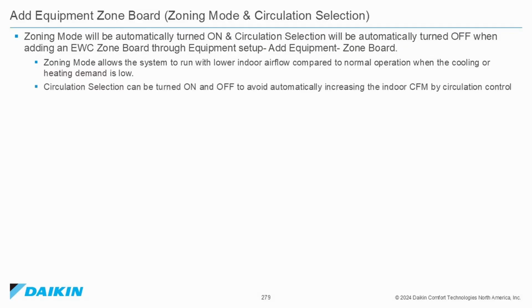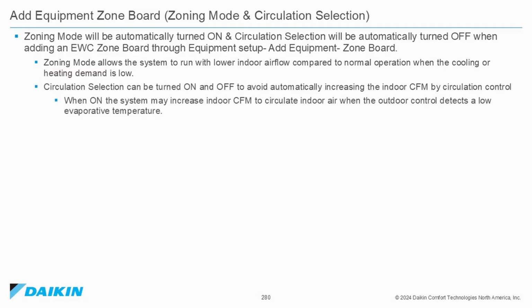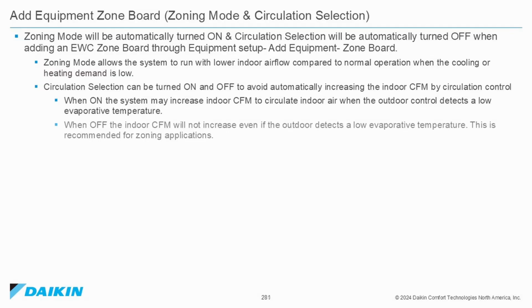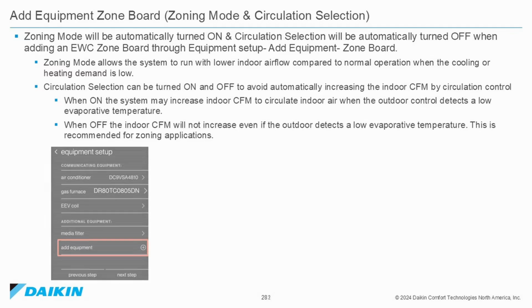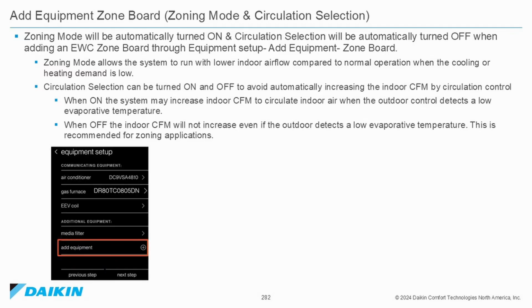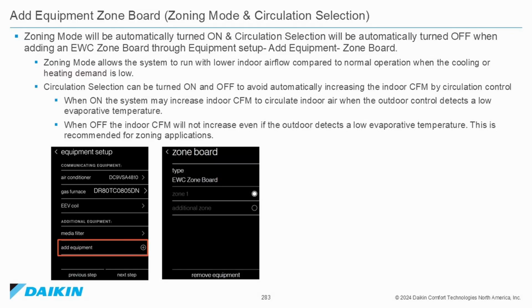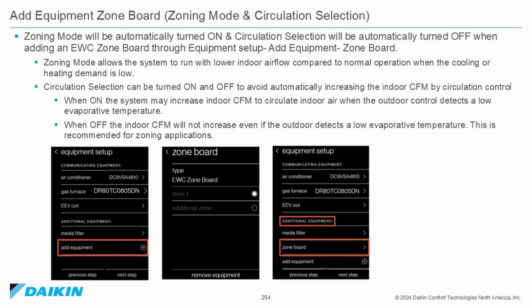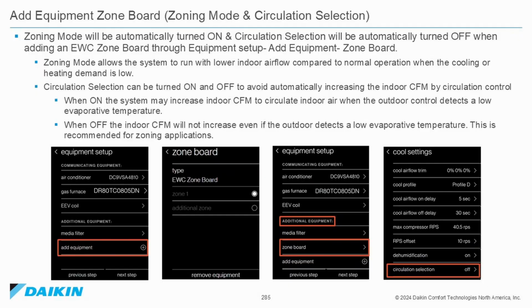Circulation selection can be turned on and off to avoid automatically increasing the indoor CFM by circulation control. When on, the system may increase indoor CFM to circulate indoor air when the outdoor unit detects a low evaporative temperature. When off, the indoor CFM will not increase even if the outdoor unit detects a low evaporative temperature. This is recommended for zoning applications. So on the zone equipment setup, click on Add Equipment, Zone Board. Additional equipment will show as Zone Board and then Circulation Selection, on or off.